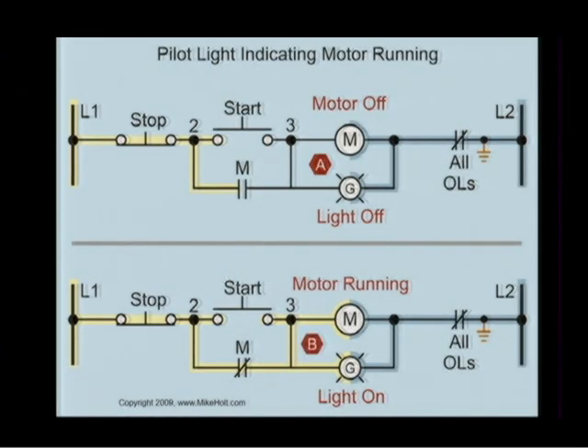Hey, lights, do they use lights? Are there certain colors that are used? Does green mean it's safe? Let me see. Green is safe. No, green means the motor's running. Red means it's not safe. No, red means the motor's... I'm missing something there. I'm confused. I think we're all missing something, Mike, because in our case, red means danger, the motor's running. Green means it's okay, the motor's stopped. Okay, so what color should this be? Is this the wrong color in this graphic? What is standard practice in the field?